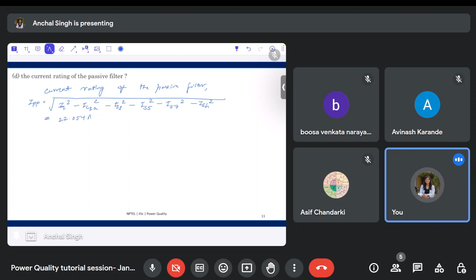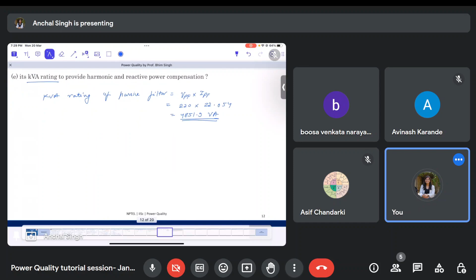And then based on this current rating, we can find the kVA rating. So the kVA rating of my passive filter will be VPF into IPF. Since this is a shunt filter, it will be 220 into the IPF we just calculated, 22.054, which will come out to be 4851.9 volt amperes. So this is how we were able to calculate the kVA rating.